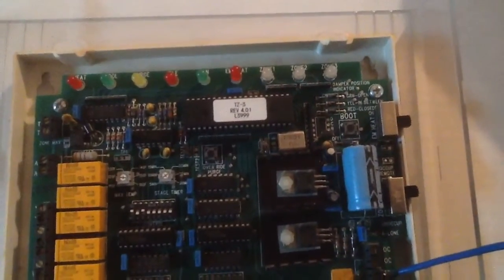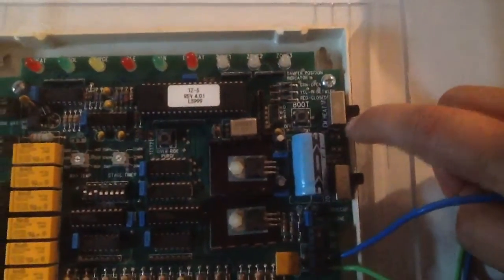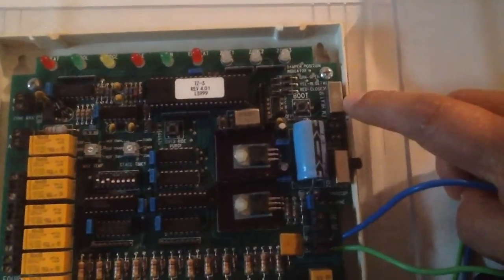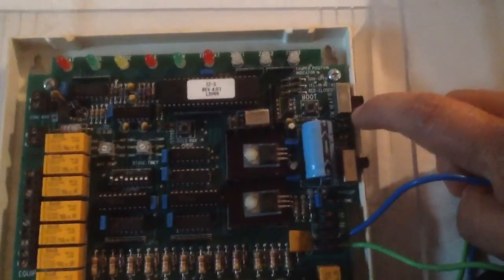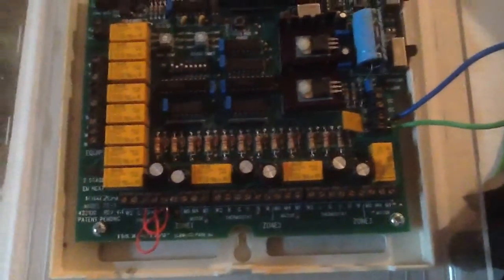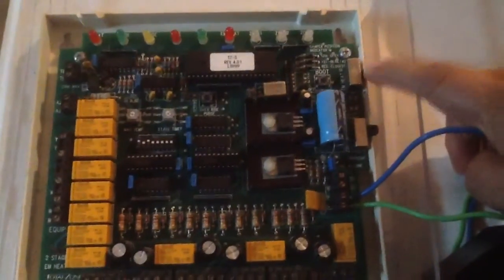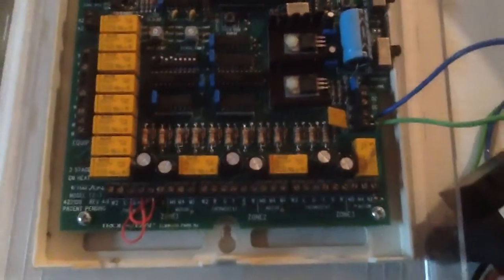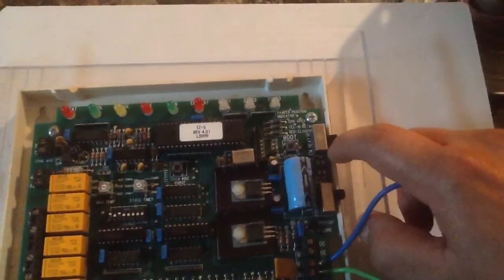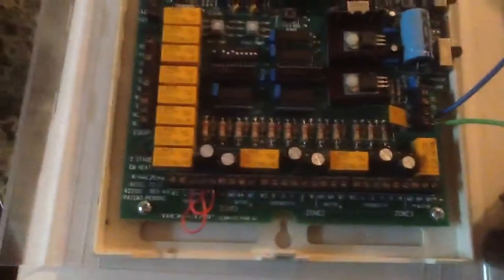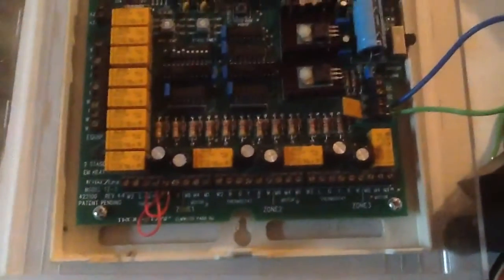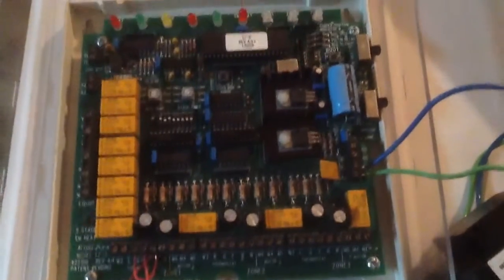And then you got a couple little dip switches over here for emergency heat. So if you got a dual fuel system or a heat pump and you switch this on, if any of these zones call for heating, even if it's first stage, it's going to run emergency. So if you got a dual fuel, it's going to run gas, even if you're calling for just first stage heat. So if your heat pump ever breaks down, you can just leave the switch on, and if any of these zones call for heat, it'll just bring on the gas. It won't even bring on the heat pump.